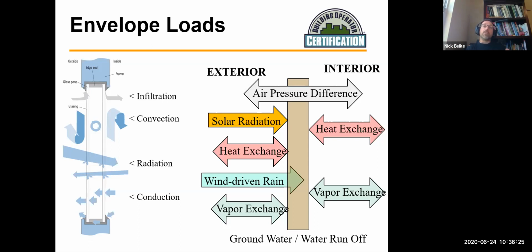That's an issue. Typically in natatoriums, which is a pool space, you want that to be slightly negative. So negative 0.04, negative 0.05 inches of water column. And if people turn them positive, what will happen is they drive all that moisture that's in the pool into the envelope assemblies. And if you've ever been in one of those pools where it looks like black mold is just growing over the top of the drywall up top, or you just see that drywall dripping down off of the walls, that's because their natatorium is too positive.